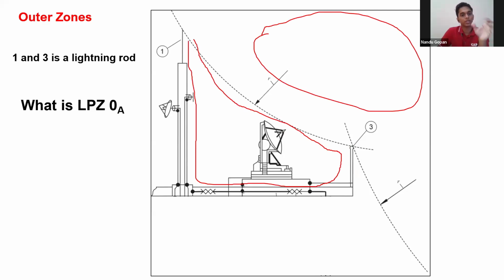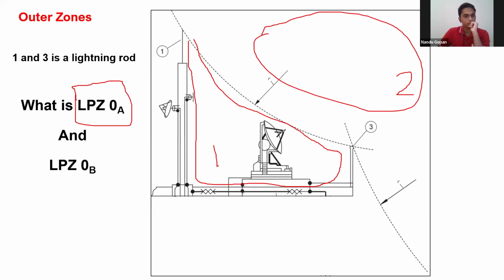So in this picture, let's concentrate only on area 1 and area 2. In this picture, what is LPZ0A and what is LPZ0B? As I told before, LPZ0A means a place where you will get a direct lightning strike. That means this area, these two, where I have marked 2, is where if anything is there, you are highly probable to get a direct lightning strike. And if you're in zone 0B, you won't get a direct lightning strike, but this equipment which is there can be subject to partial lightning current.